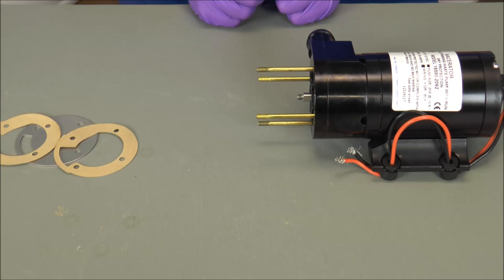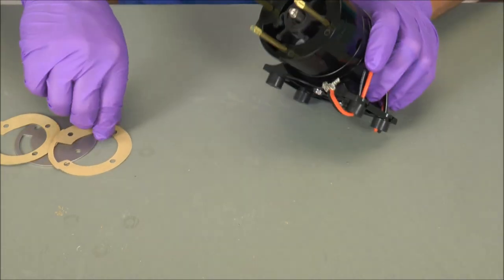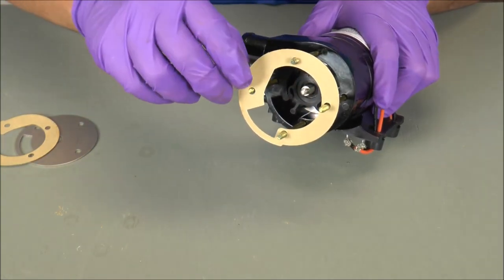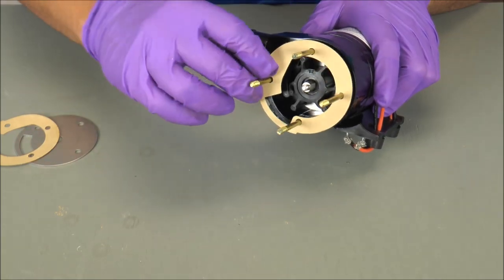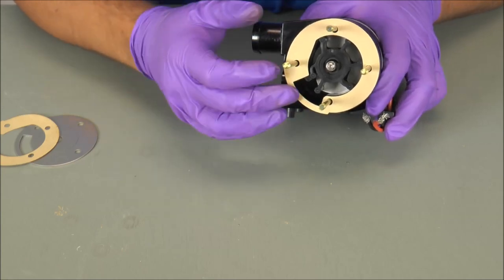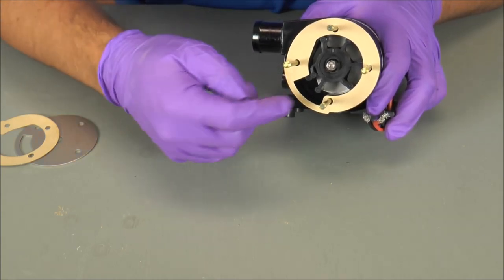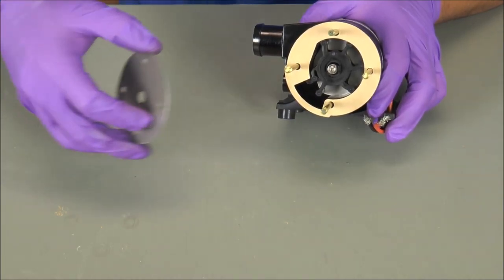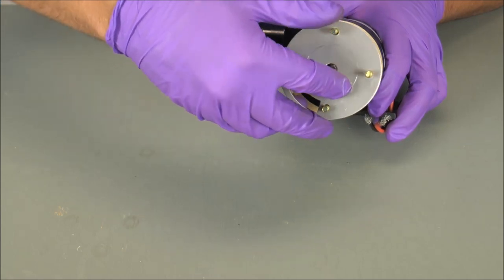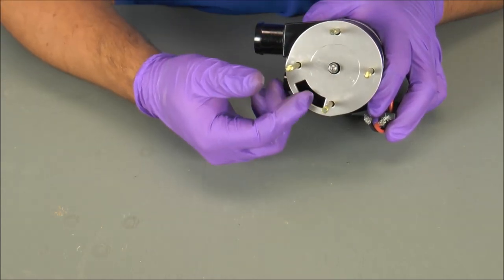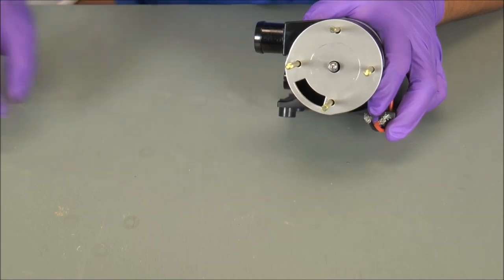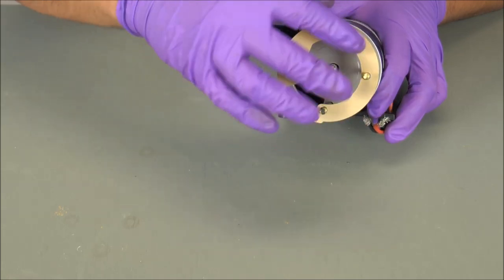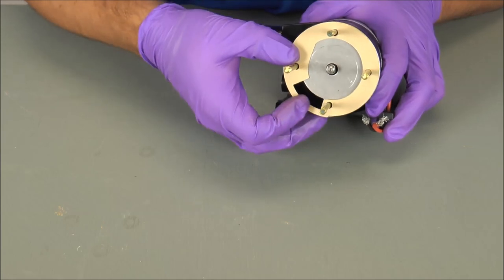So now we're going to reinstall the two paper gaskets and the large wear plate. First things first, paper gasket goes on first, and you want to make sure that the cut out of the paper gasket matches the cut out of the impeller housing. After the first paper gasket comes the large wear plate. Again, that opening matches the same opening of the impeller housing, and then last comes the second paper gasket, keeping in mind that the cut out matches the same cut out of the impeller housing.